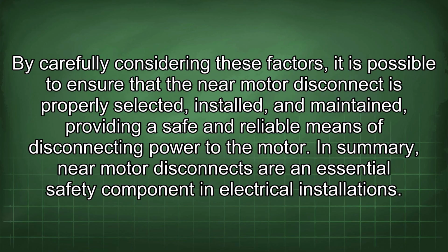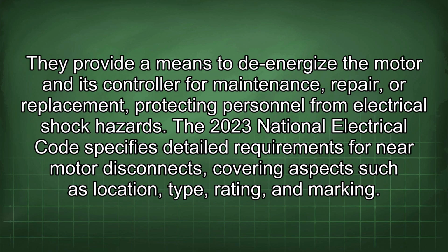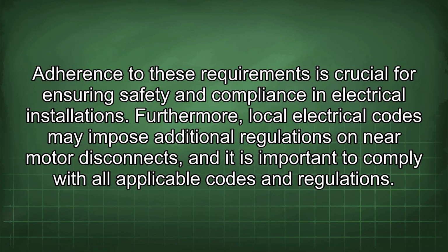In summary, near motor disconnects are an essential safety component in electrical installations. They provide a means to de-energize the motor and its controller for maintenance, repair, or replacement, protecting personnel from electrical shock hazards. The 2023 National Electrical Code specifies detailed requirements for near motor disconnects, covering aspects such as location, type, rating, and marking. Adherence to these requirements is crucial for ensuring safety and compliance in electrical installations.